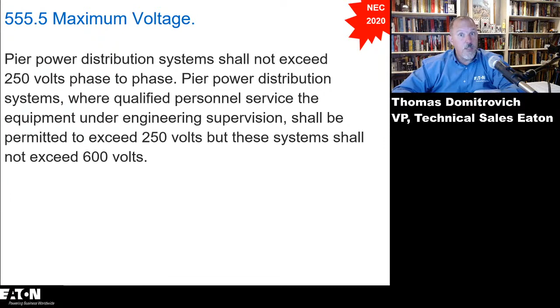But still, we had that into consideration, and you're not allowed to have more than 1,000 volts the way we wrote it. The power distribution system shall not exceed 250 volts phase to phase. Where qualified personnel service the equipment under engineering supervision, they are permitted to exceed 250, but not 600 volts. And in that decision, we did consider those big boats, and they are powered at typically around 480. They're not 4160. They don't take medium voltage onto those boats. So there's no reason to get 480 out there.